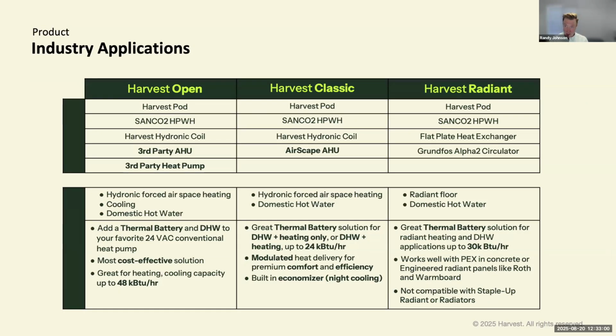Very good question on both of those. The Sanco 2 heat pump system has a cold climate variant that's available in Colorado. It operates and provides hot water down to -25, which is pretty incredible. It doesn't even derate till about -5 degrees, if I'm not mistaken. From an overall design and resiliency perspective, Sanco 2 has redundancy in freeze protection. There's two ways that they go about it. They do have electric resistive tape that goes around all the hydronic lines coming into the house. That is actually powered directly off the outdoor unit, so you don't actually have to run electrical for it. So it makes it very, very easy to add that into a project.